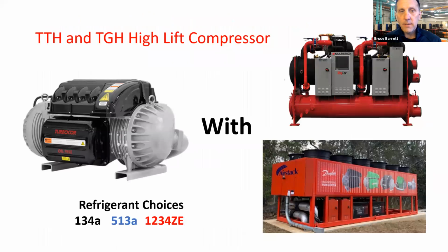So the machine on the upper right, we're just taking that high lift compressor and we put it on a set of shells. So if you've got a large enough load for 100 to 1,000 tons, we can employ this chiller on a water-to-water heat recovery application, or again, with the high lift air-cooled machines. Because we have approximately 100 tons per compressor, we can unload to that one compressor operation and still maintain the temperature leaving that machine versus a single compressor or dual compressor machine that cannot unload very, very well.